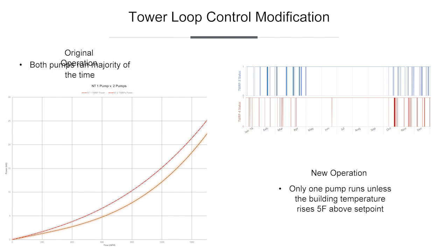Very similarly, condenser water pumps out at the other tower, common configuration. There were 2 condenser water pumps in parallel. As his condition was, and this took me a while to read his graph, pumps are on, these lines are when the pump is momentarily turned off, but then, summertime, it is 2 pumps running constantly. Now, if you look in the ASHRAE publication, it will tell you if you've got 2 pumps in parallel on the system, that second pump really is, you're going from a 1.0 pumping to maybe a 1.4, theoretically.